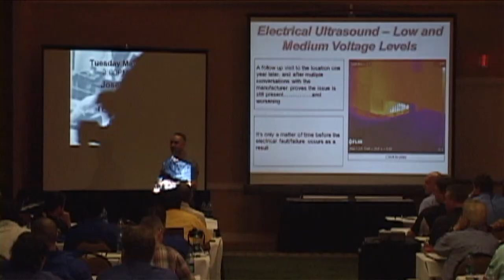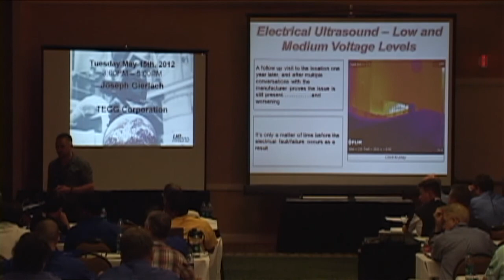For transformers, you take the sound from this transformer — typically dry type transformers are enclosed. I saw the pictures early on, you can actually see some little gaps, but normally it's in the top or the bottom, there's a little bit of race. What's your SOP for taking the three coils? Do you position approximately where the sound needs to be, or take a lever up and point it down? It depends on the transformer, but typically you have convection air vents on the dry units, so it's easy to use the airborne sensor and do a very panoramic scan of the entire unit on the top and the bottom.